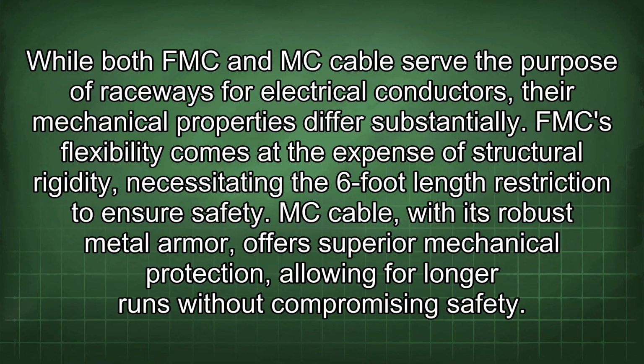While both FMC and MC cable serve the purpose of raceways for electrical conductors, their mechanical properties differ substantially. FMC flexibility comes at the expense of structural rigidity, necessitating the 6-foot length restriction to ensure safety. MC cable, with its robust metal armor, offers superior mechanical protection, allowing for longer runs without compromising safety.